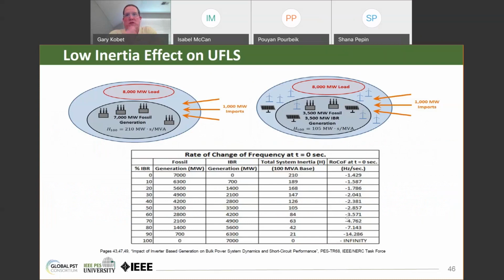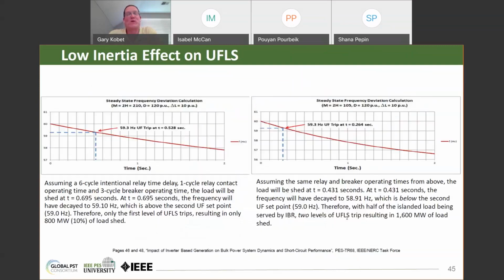With the total system inertia of 210, the rate of change of frequency is 1.4 hertz per second, and with half of the system being inverter-based resources, 3,500 megawatts of conventional and 3,500 megawatts of IBR, the rate of change of frequency increases to 2.8, which is double. So if you go back to the previous slide, please, I apologize. I have those out of order.